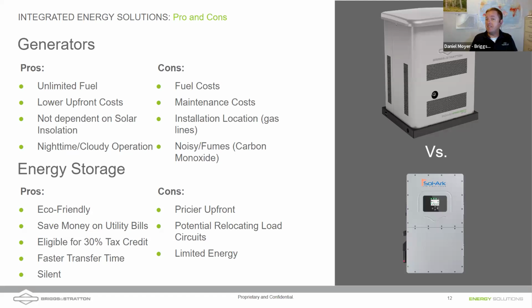Installation location is going to be dictated by where those gas lines are, and whether you want the generator pointed towards your neighbor if you don't like them, or somewhere else if you do. Noise is always a concern with generators, and also fumes. It's not necessarily the fault of the generator manufacturers, but installers installing generators too close to openings in homes have caused carbon monoxide poisoning in people's houses.